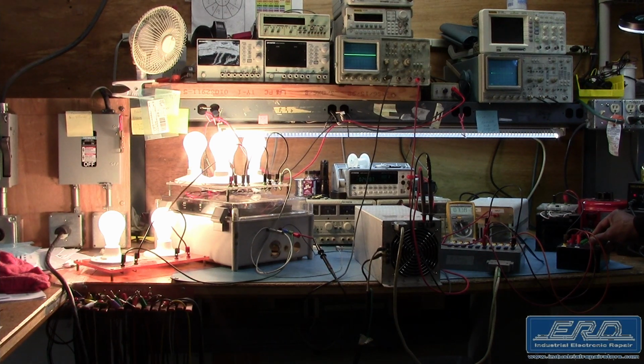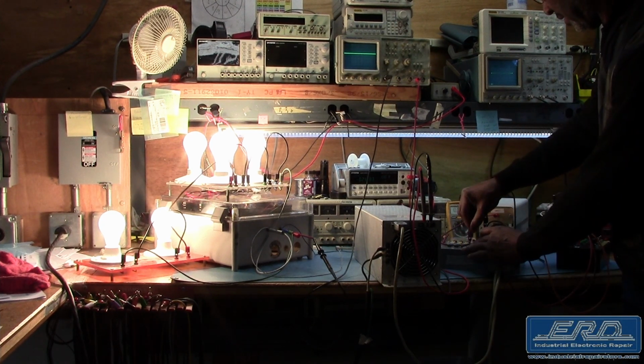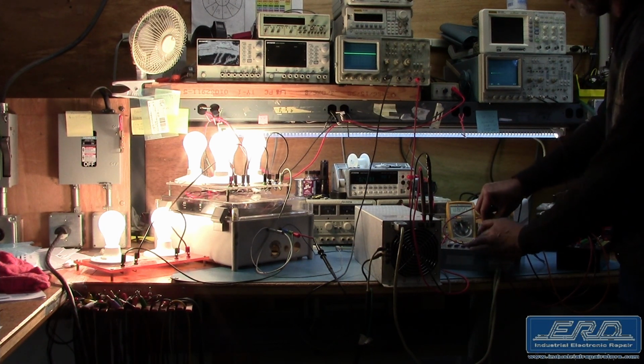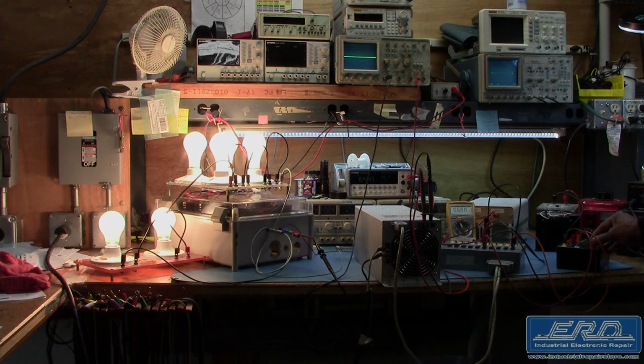And as shown in the video, we slowly ramp up the output before we run it, as in the field, where it switches its full voltage output as the laser pulls power from the capacitor bank. Most industrial lasers require high voltage capacitor banks, and we can configure tests for the majority of the sizes used in the industry.